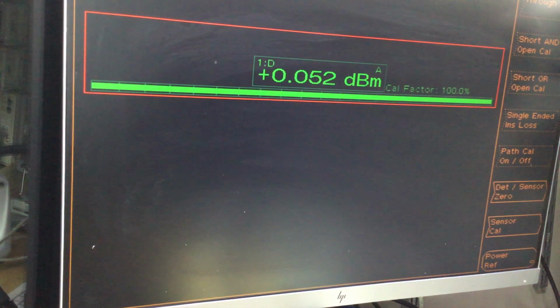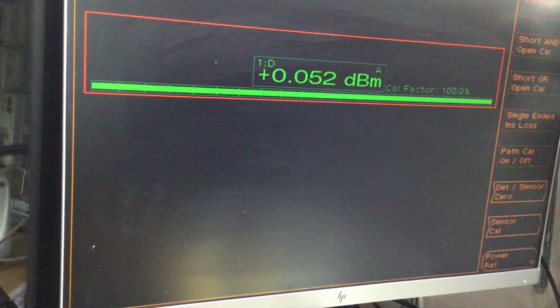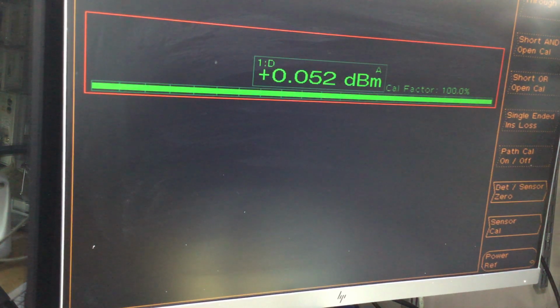So considering this, according to the label on the front of the meter, this HP meter was calibrated in 1999. So it's not bad, you know, considering it's 25 years since it last had a cal, and it's plus 0.052 dBm. And so we can adjust that probably and get that bang on 0 dBm, so it matches the Marconi as well. So we could do that for my friend's meter.